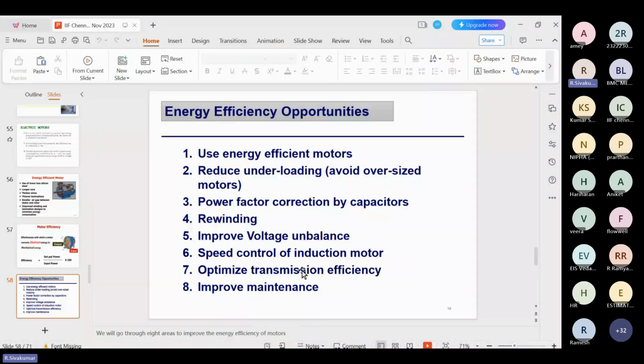And rewinding is also considered. More than three rewindings should not be permitted within the industry, so a proper logbook and history book should be maintained for each and every equipment. Only then can we find out how many times it was rewound. Without data, without a history logbook, we cannot find out the rewinding history. And improve the voltage unbalance and the speed control of the induction motor by adopting a variable speed drive or variable frequency drive, and optimize the transmission efficiency.